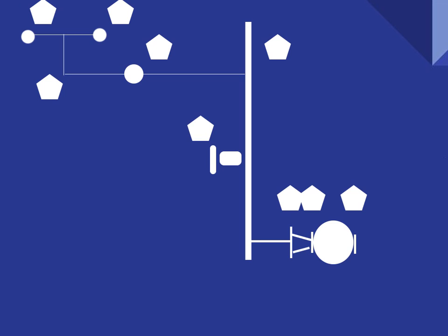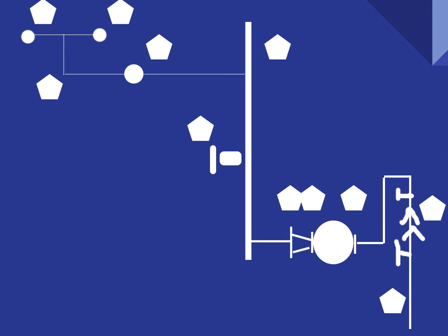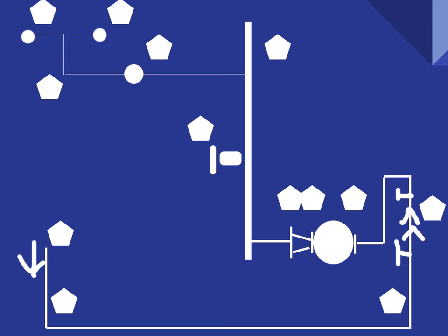The nodes for the heads in the remote areas, the nodes for the accumulation of the remote area's flows, the nodes for a change in size to a cross main, the node for a change in size to the standpipe, the node for addition of inside hose allowance, the node for a change in pipe size at a concentric reducer, nodes for both the discharge and suction flanges, a node for the backflow preventer for the loss curve, a node for the connection to the underground pipe, a node for the change in underground pipe sizes, and finally a node for the tested supply point, the origin of our flow.